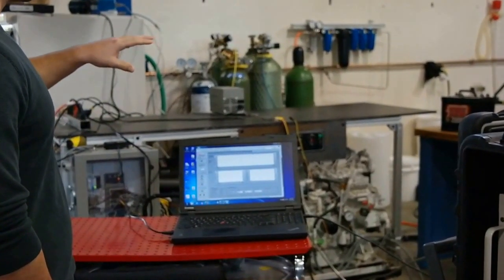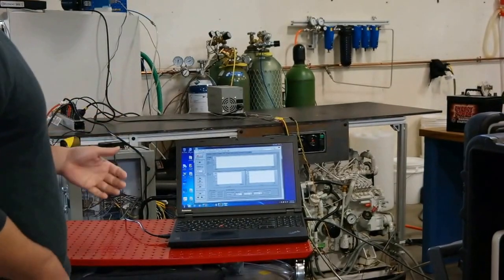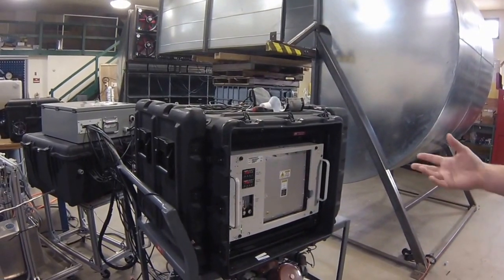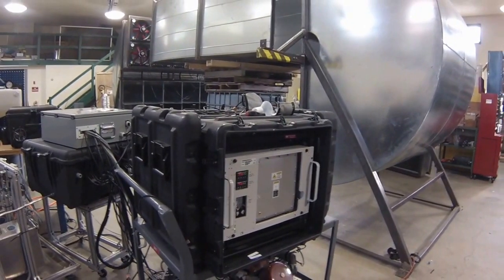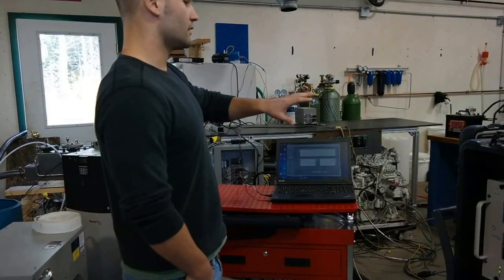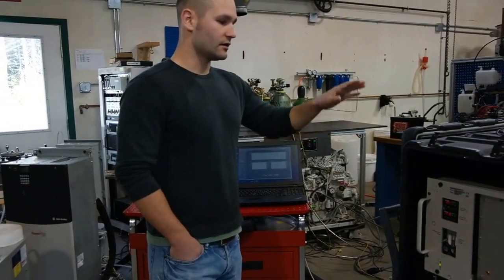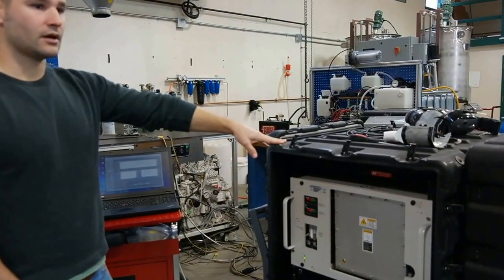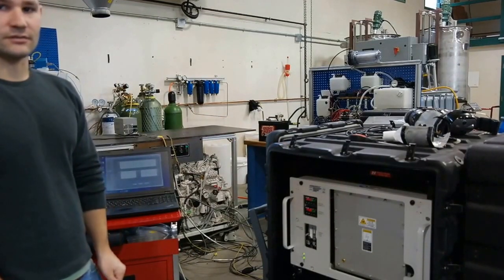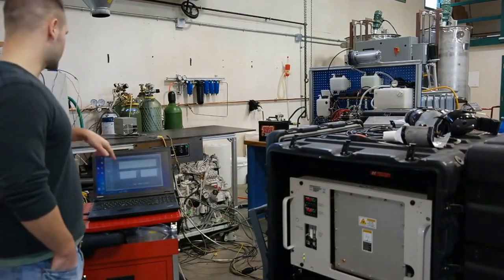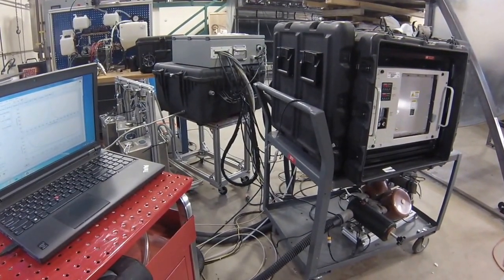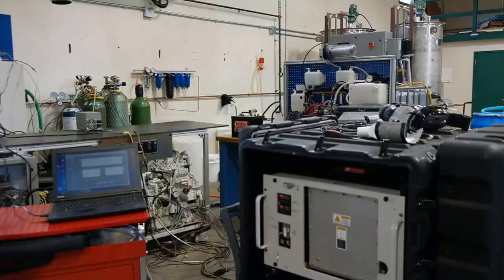It's outfitted with various performance and emissions monitoring equipment. In terms of the emissions equipment, we have here a Fourier transform infrared spectrometer, which measures all of our gaseous emissions. That is hooked up through these heated lines here to the exhaust of the diesel generator.